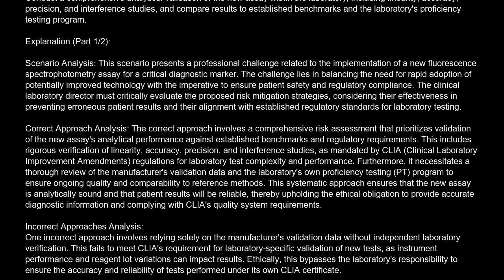The correct answer is A. Conduct a comprehensive analytical validation of the new assay within the laboratory, including linearity, accuracy, precision, and interference studies, and compare results to established benchmarks and the laboratory's proficiency testing program.